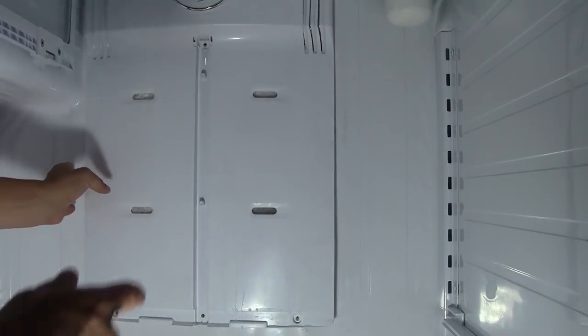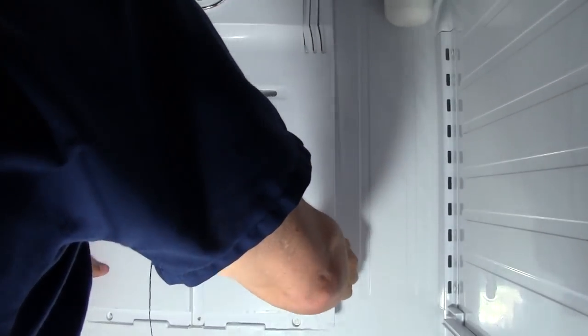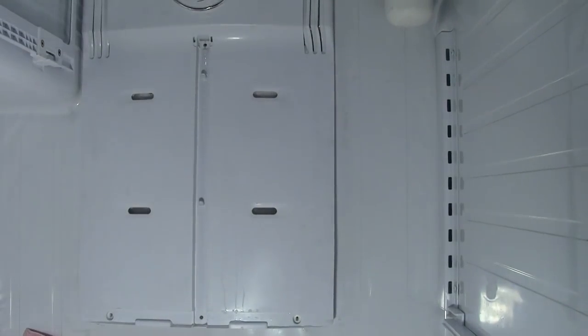Okay, let's not waste any time. As you can see, I had some ice built up and it's the usual. You start to hear that grinding noise, a fan that sounds like a baseball card in the spokes of a bicycle. When you hear that sound, you know that the ice is building up and eventually the fan is going to stop.